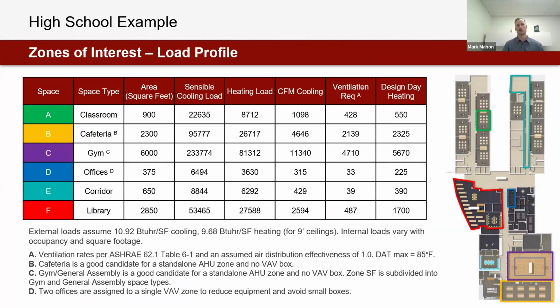But I'm looking at a few zones of interest. So a classroom space, a cafeteria, a gym, offices, corridors, and a library. And of course, would I actually, as an engineer of record, serve a gymnasium with single ducts? No, I wouldn't. I would use an air handler as a designated zone, likely, if this was the system type I was using, but I wanted more zones so I could get more data. So forgive me for my design mishap here. Of course, it would be a good candidate for a standalone AHU or packaged RTU, but I'm doing VAV boxes because I hold the keys to the kingdom at this point, and that's what I decided.